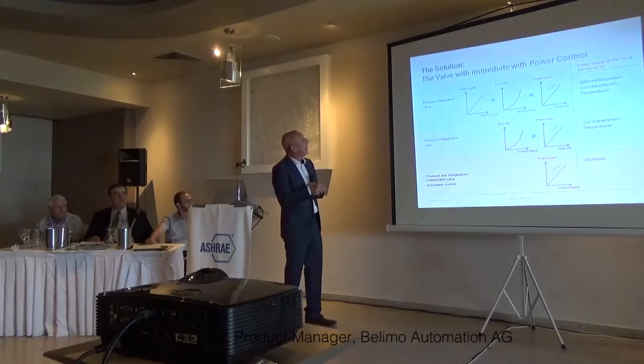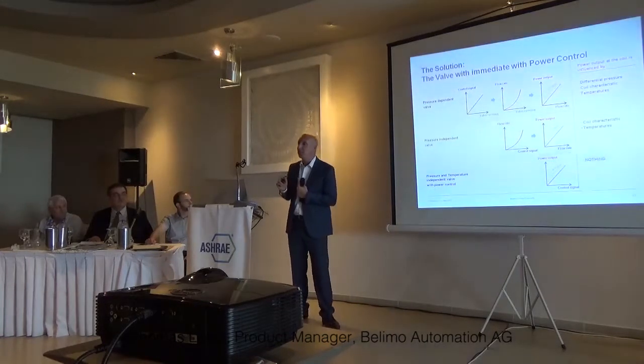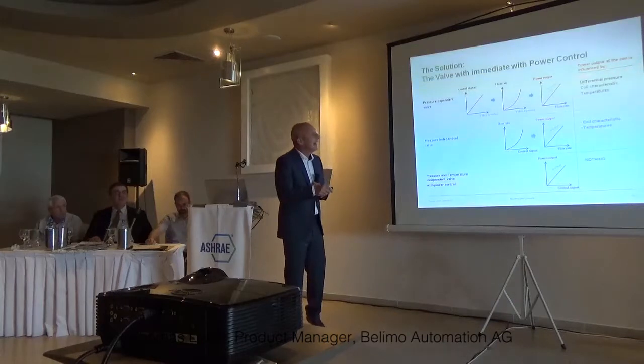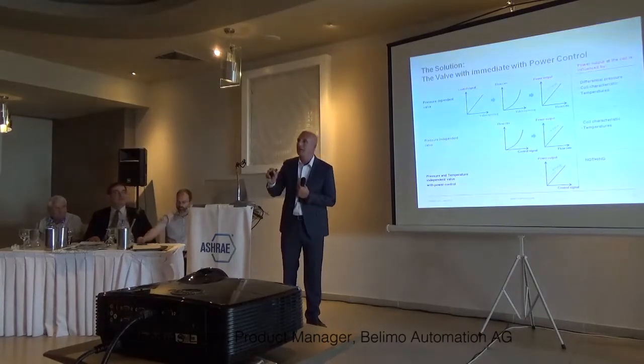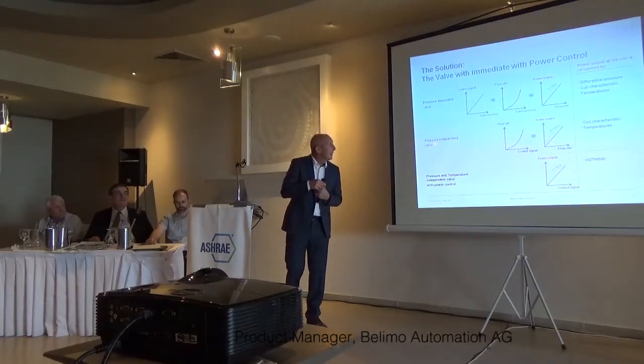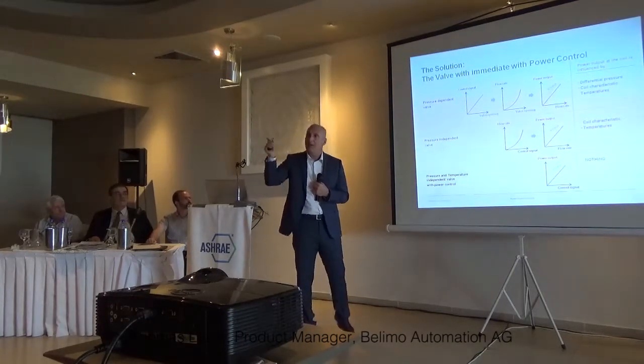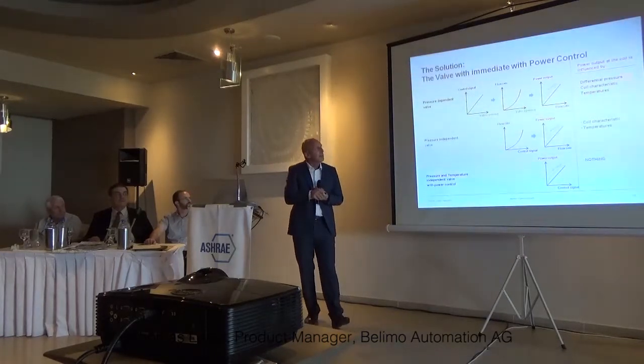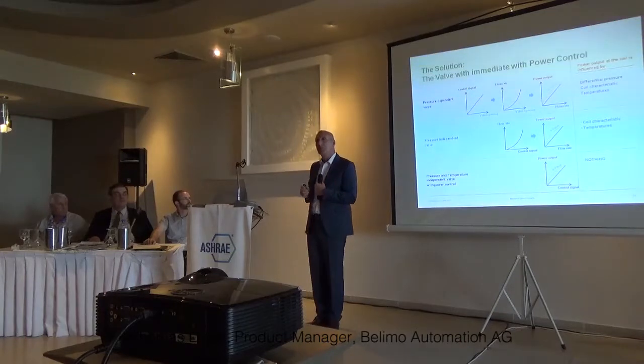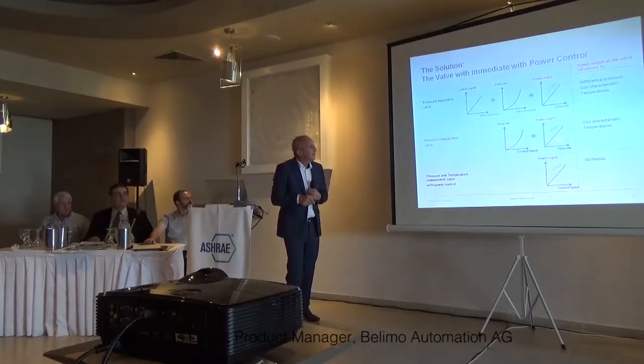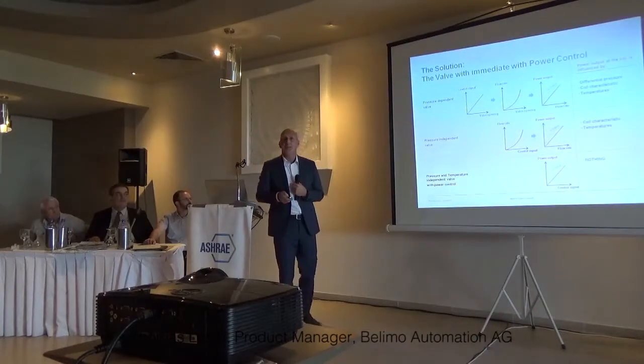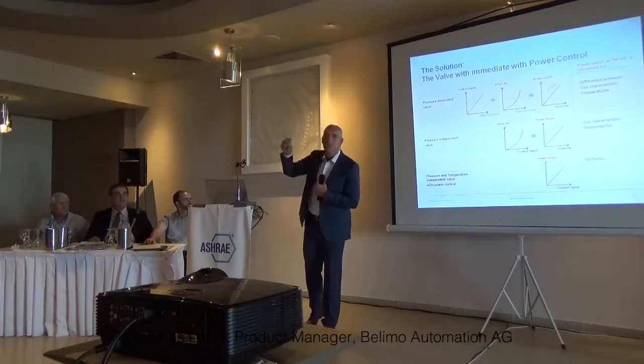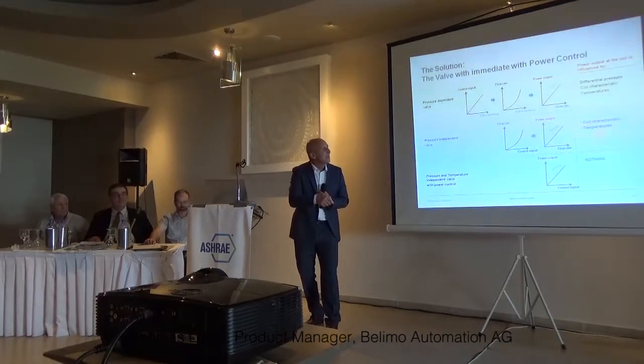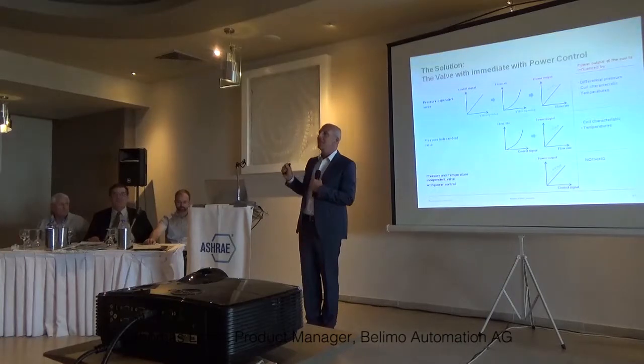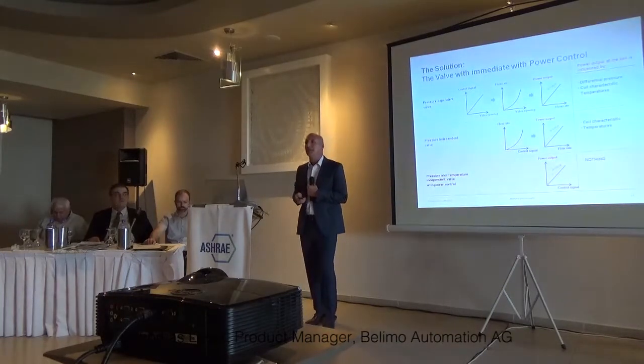So, to resume. Simple and stupid valve, you need at least three steps to get the power into your room. There are a lot of influencing issues. With the pressure-independent valve, you refer immediately a control signal to a flow. That means you can skip caring of the pressure changes. Once you could go straight away to power control, you can cover now all these temperature issues and also the problems that you might have with your air handler or with your fan coil.